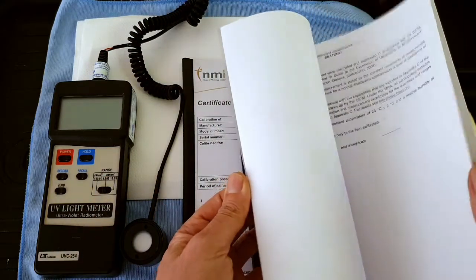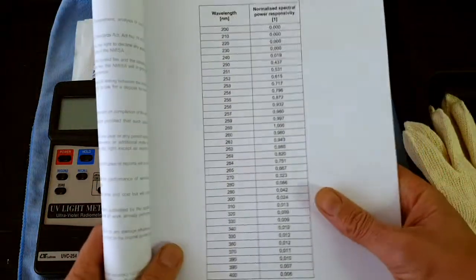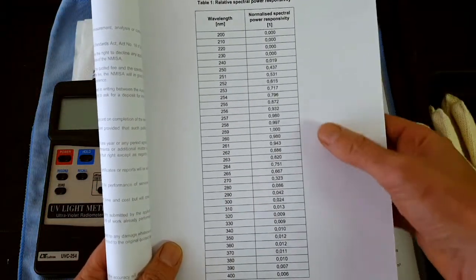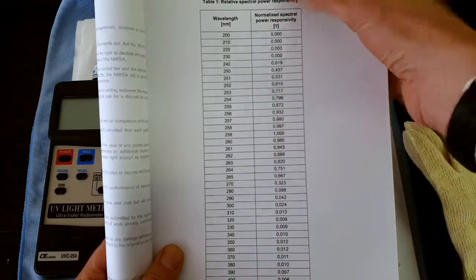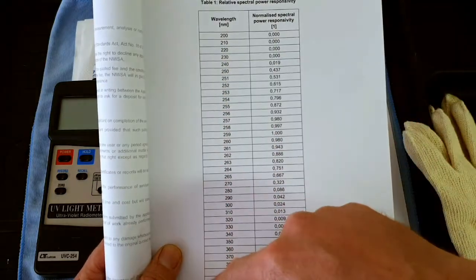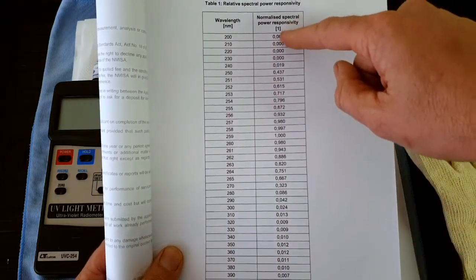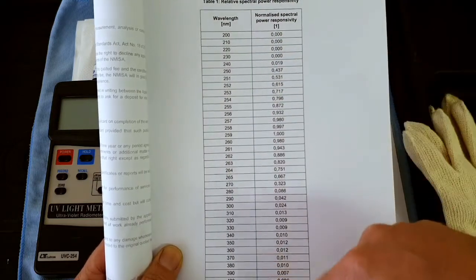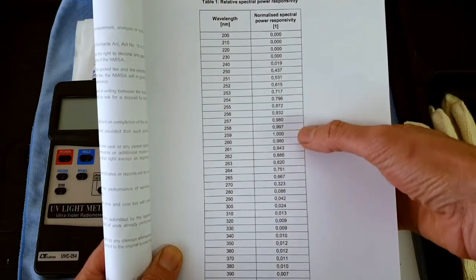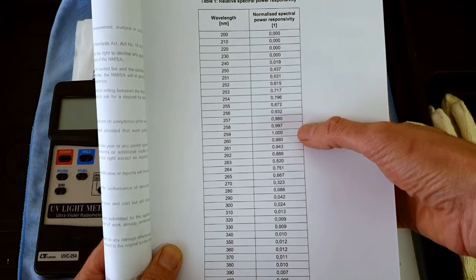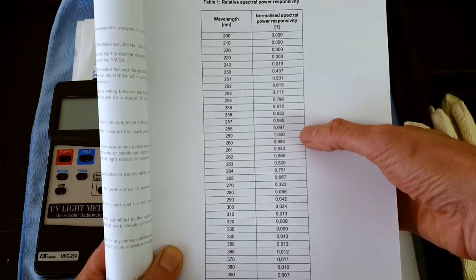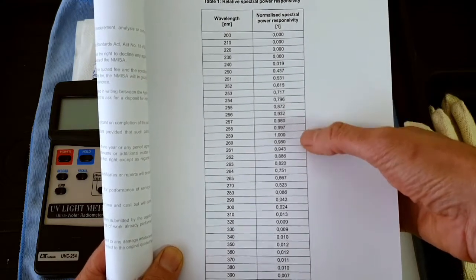So out of curiosity, what we did is we took this sensor, or this device, and we did a full spectral calibration on it. And what you'll see is that value over there. So this is the individual wavelengths that it was calibrated at, and this is the power responsivity. And its peak responsivity is at 259 nanometers, not at 254. Not too bad, it's pretty close.